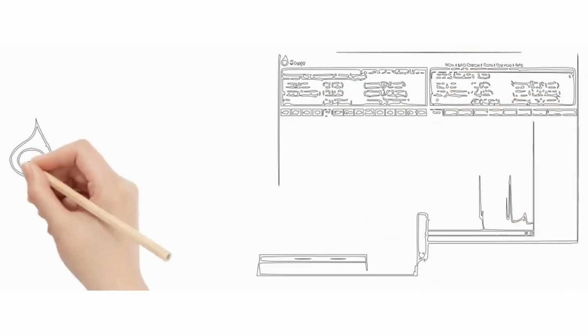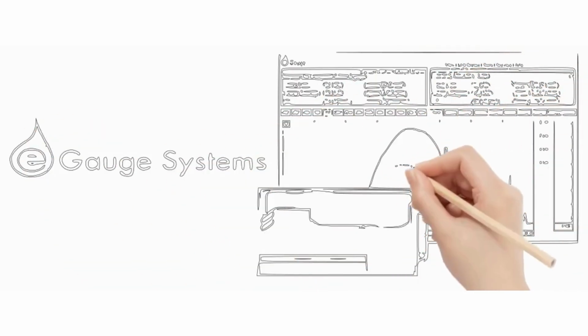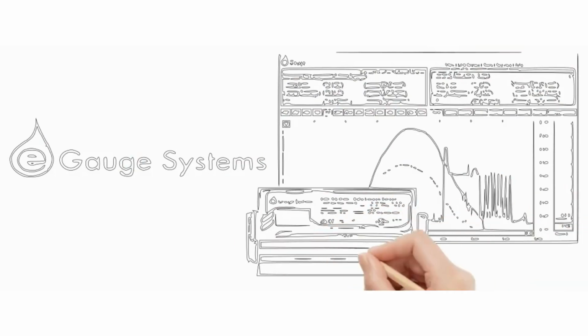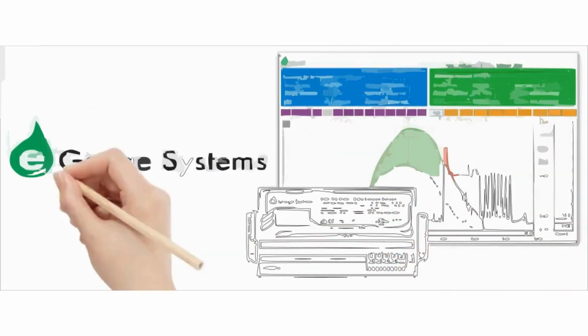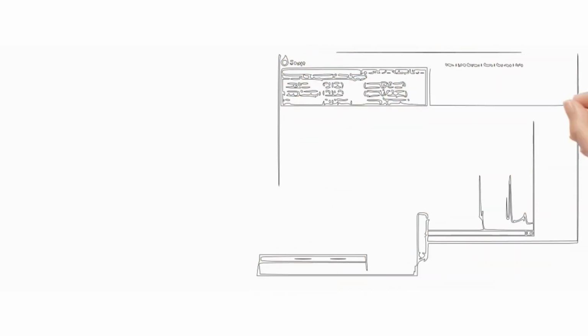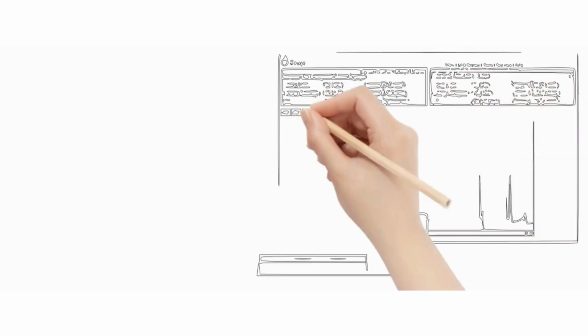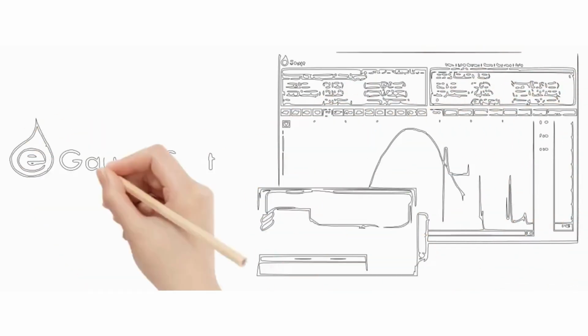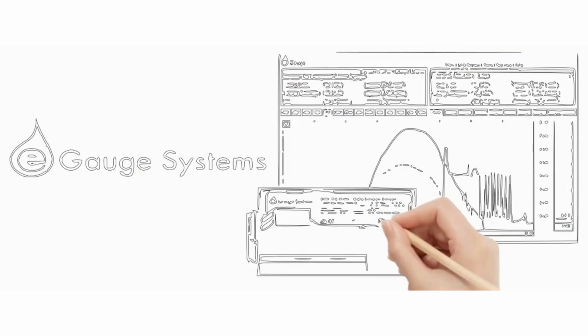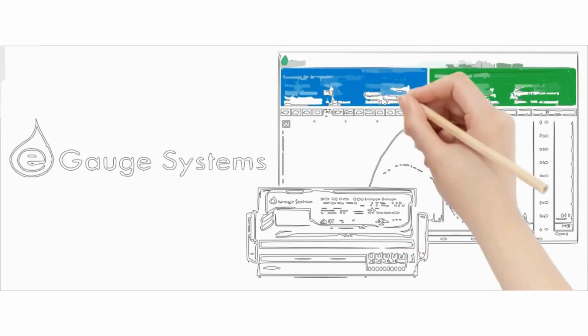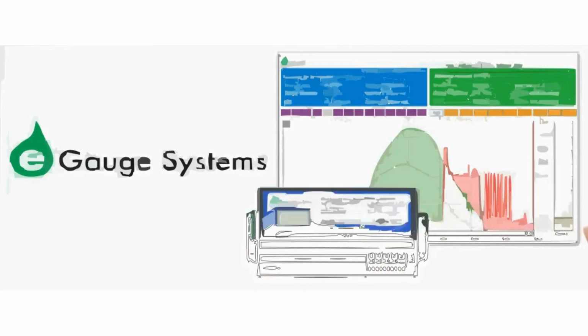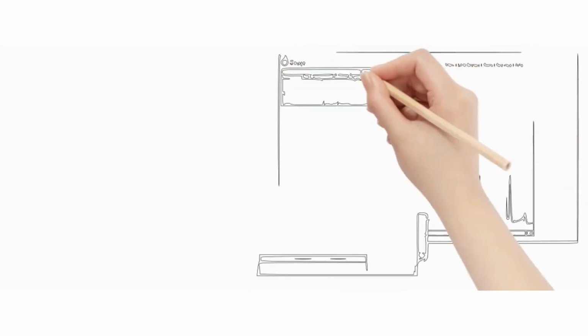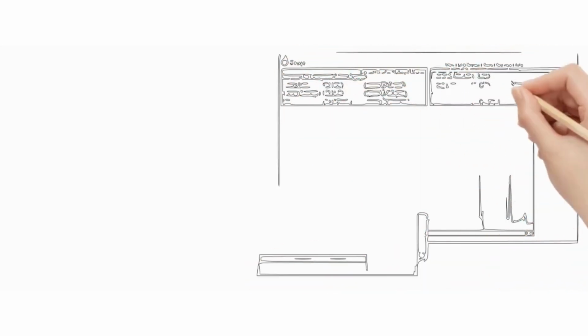That's the core difference that separates modern e-gauges from older meters. If you don't sample super fast, like 128 or 256 times per electrical cycle, and perfectly simultaneously across all the phases, the power calculations you make later are fundamentally inaccurate. It's like timing a three-person race with three separate stopwatches started at slightly different times. You won't know who really won.